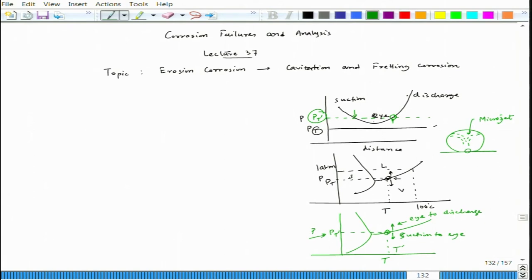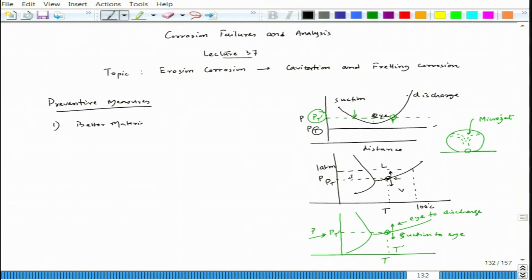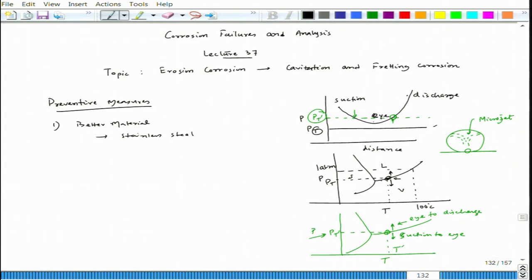To find ways to prevent cavitation, the first preventive measure is using better material. Since we cannot always stop bubble formation — in pumps or in propellers moving at high speed — we need a material with higher cavitation resistance. Stainless steel has very good cavitation resistance compared to carbon steel; it has extremely high cavitation resistance relative to carbon steel.